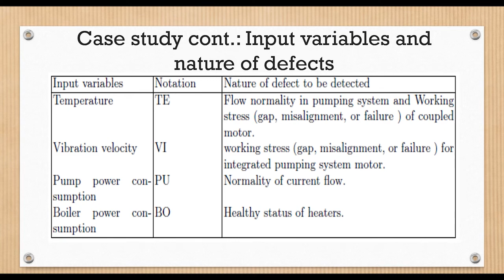With those 4 variables, we can detect water flow normality, working stress of the motor, power consumption, and boiler status. These tables respectively show the input and output variables' healthy range. The value ranges that reflect fault severity levels and maintenance priority indices are classified by considering previous available data recorded during regular inspections by maintainers on a time basis.